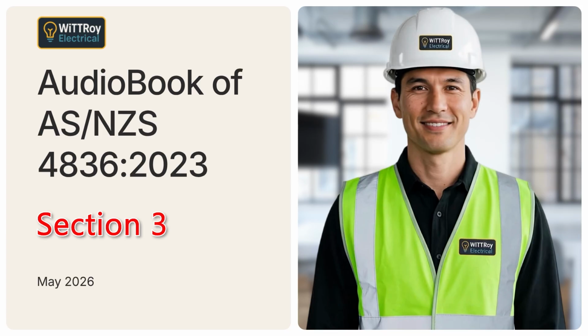The strongest message is simple. Identify the correct equipment. Isolate it from all energy sources. Secure the isolation. Prove it is de-energized. Control nearby live parts. Use suitable test equipment and PPE. And never assume equipment is safe just because it appears to be switched off.